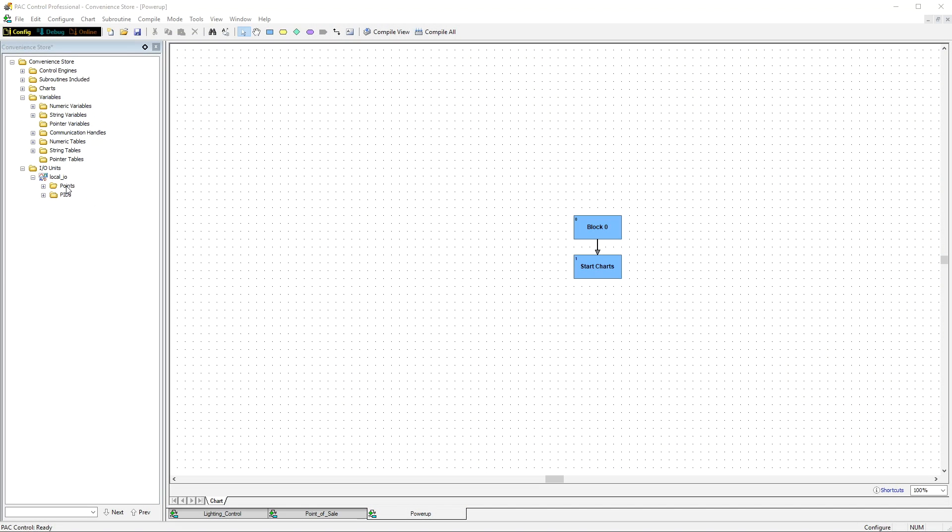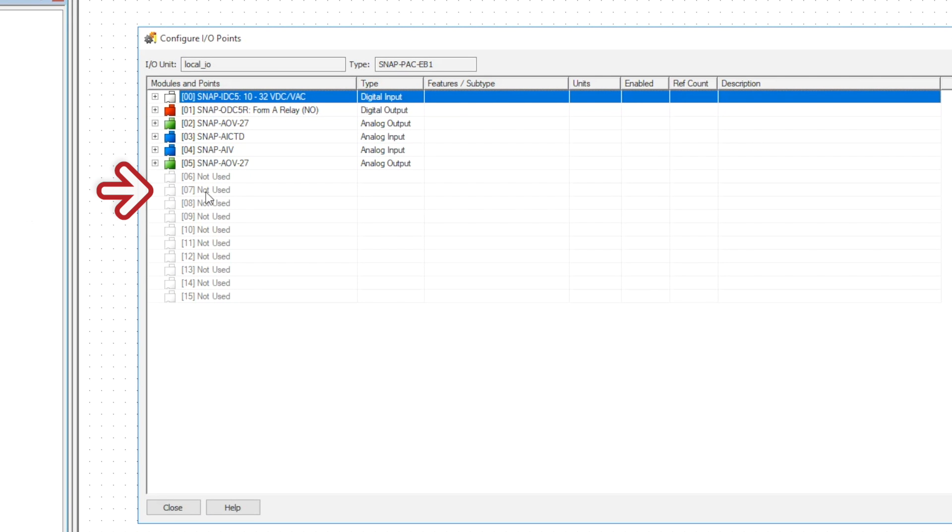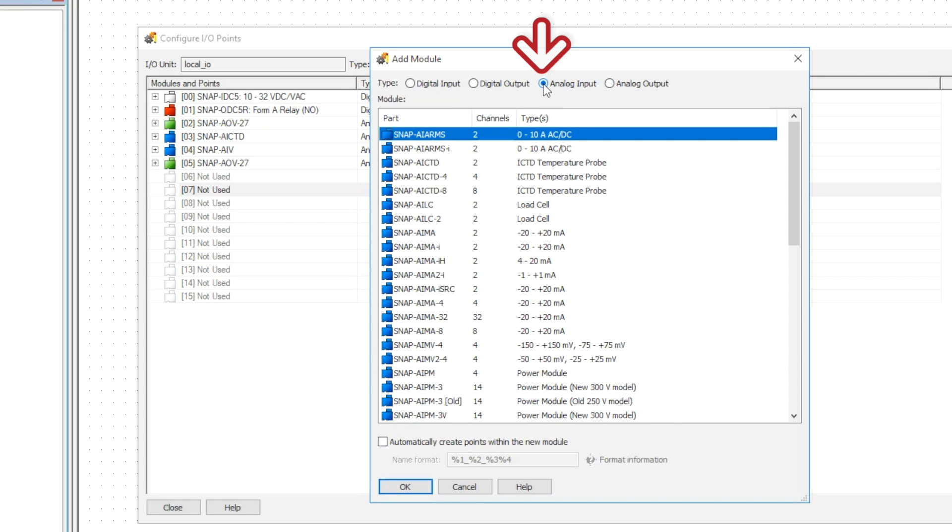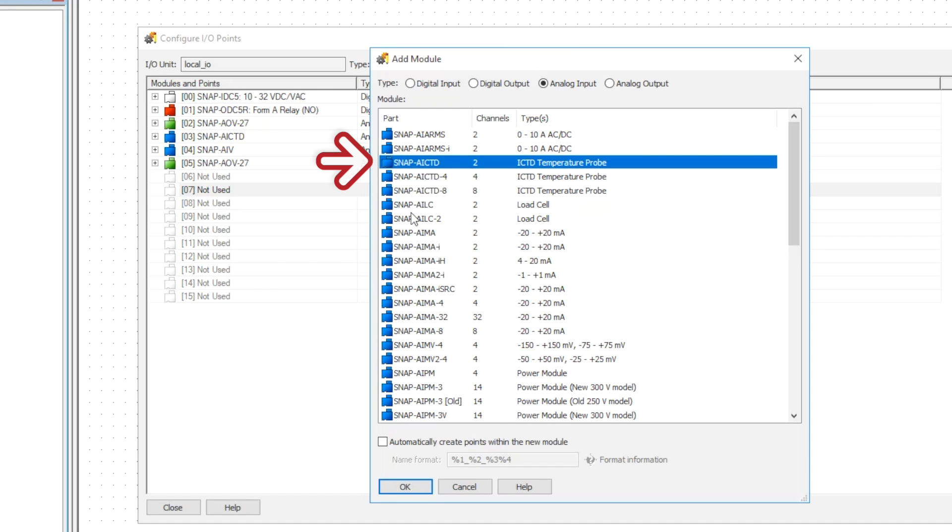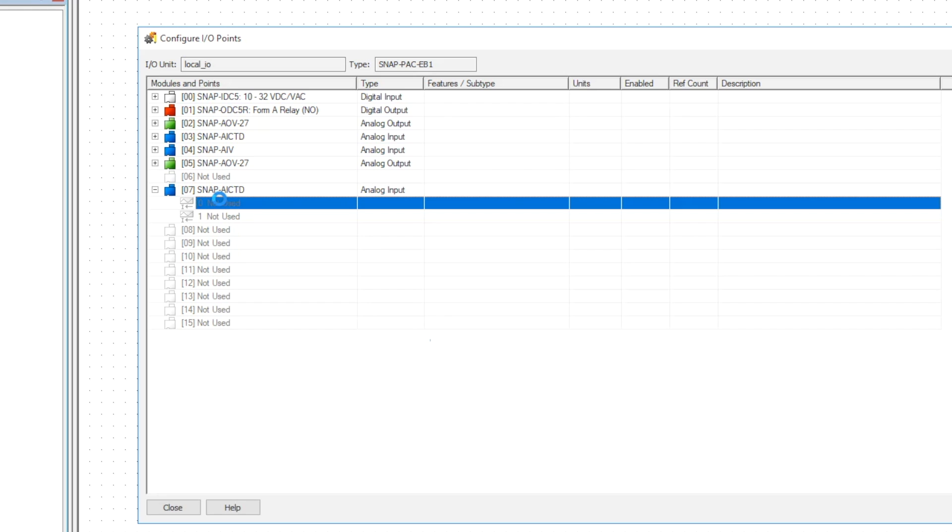Here we are in PAC control, and we've already got our rack configured, so now let's double-click on the empty slot in position seven and we're going to add an analog input temperature module. In this case it's a SNAP-AICTD, and we're going to double-click on the first point on the module to open the point configuration dialog.